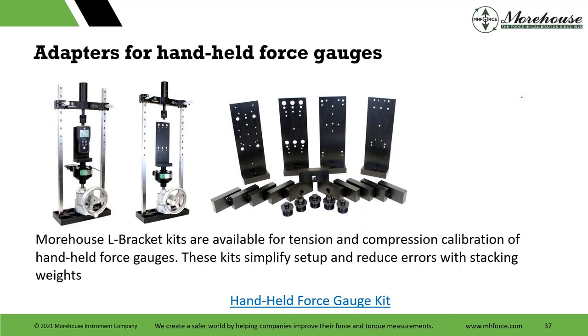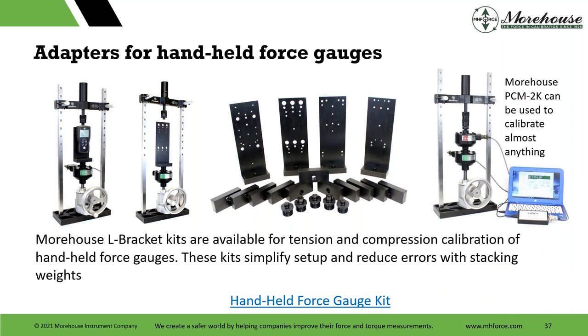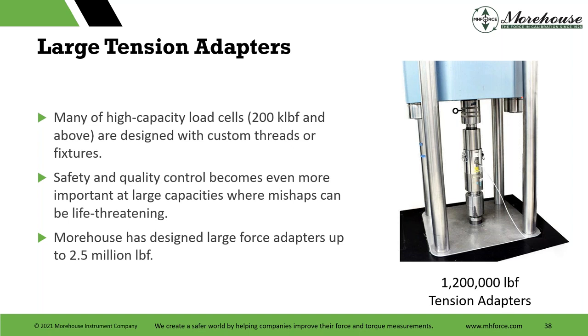When you go to low forces, you should switch to this portable machine that goes up to 2,000. I can't recommend enough that this setup on these smaller machines is preferred for handheld force gauges, rather than trying to do that in the UCM. You can also do small load cells. So with a 100K UCM and a 2K PCM, you're going to be able to handle a lot of equipment, from capacities of at least 10 pounds all the way up to 100,000. As the workload progresses, we often recommend adding another UCM around 30,000 or 10,000, depending on where your workload is. And there are large adapters we can design, and we design huge machines. We can design machines up to 3 million pounds of force.